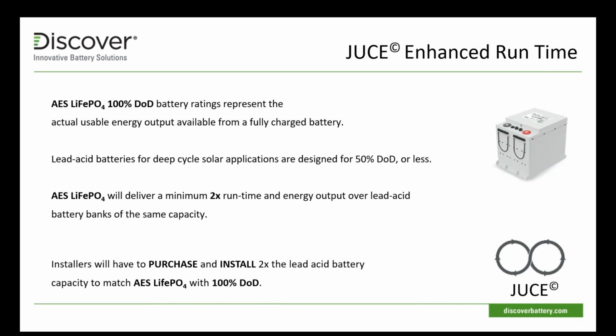So the feature functionality that we've termed JUCE, really enhanced runtime there, really talks about the usability of capacity. So we have 100% depth of discharge capacity of this. So the 6.6 kilowatts is available to you, and you can go to 100% of depth of discharge. Unlike the lead acid batteries that commonly using are usually around 50% depth of discharge, potentially up to 80% depending on the type and style in there. This means that double the energy is available to you in the same amount of kilowatt nameplate rating there. So be purchasing less kilowatt hours to get the same amount of energy out and same kind of runtime.